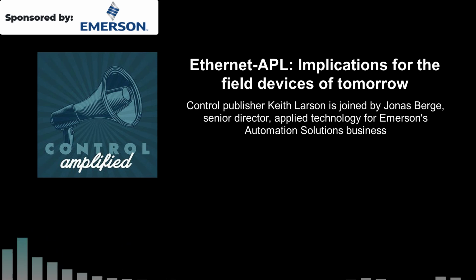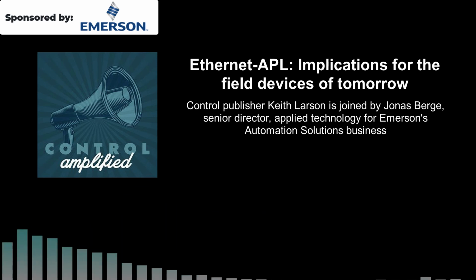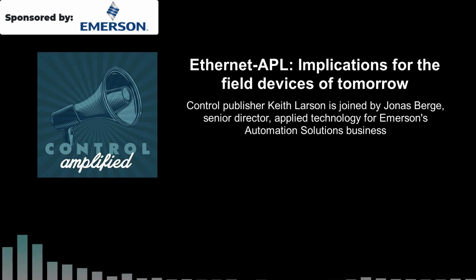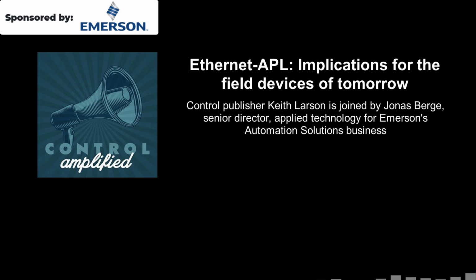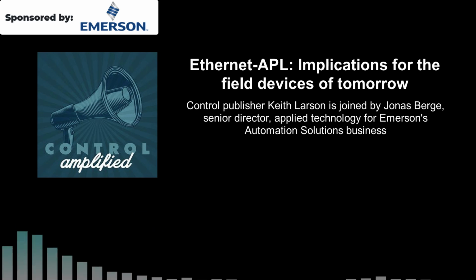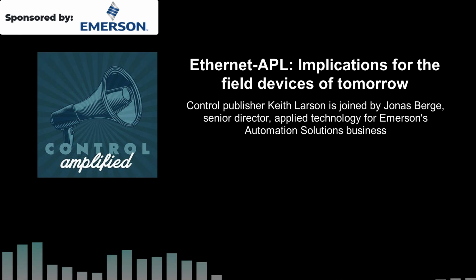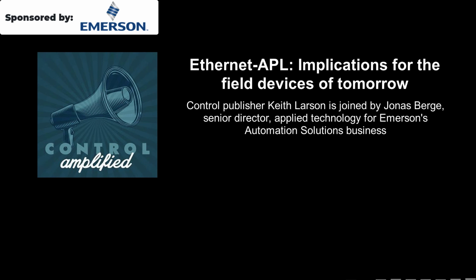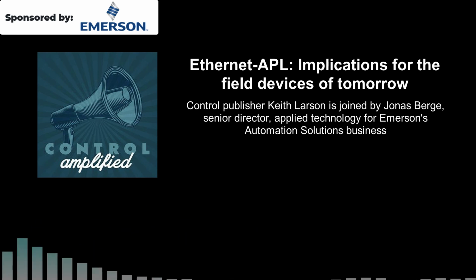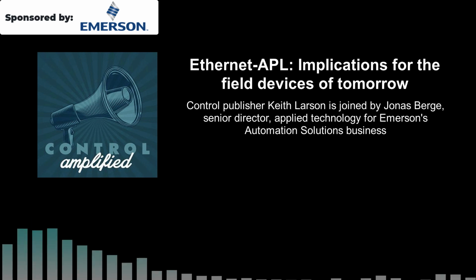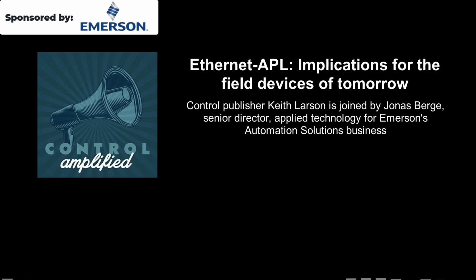The beauty with APL is that the switch is really like a switch. Each device sits pretty much on its own network, or spur, if you will. So if noise makes its way into one device, it only affects that device—it doesn't propagate to the others. The network becomes very robust, and it becomes very evident where the noise is getting in, so it's easier to troubleshoot.